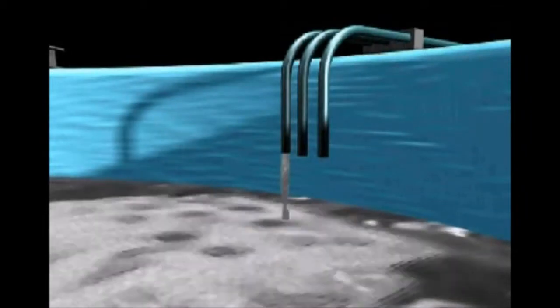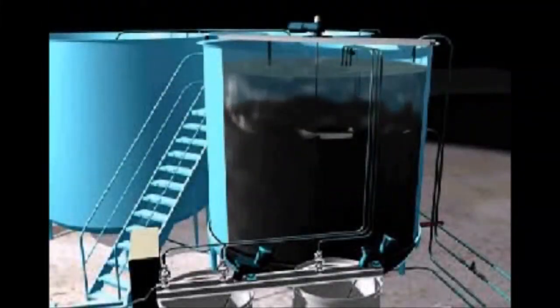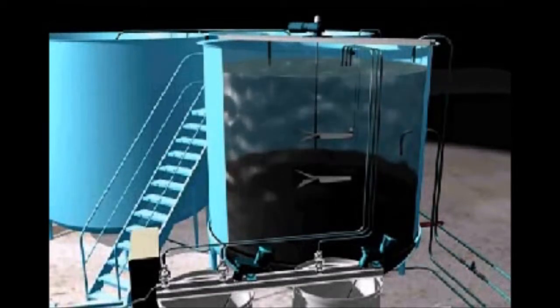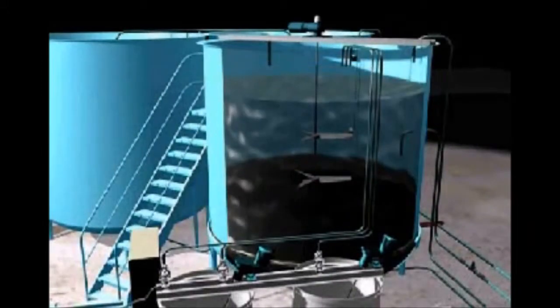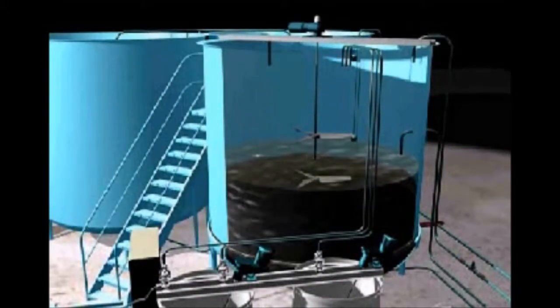The flocculant is then added by volume, after which the mixer turns on for a short time to mix the contents of the tank. The flocculant enlarges the coagulated wastewater for ease of settling and the ability to dewater the sludge in the filter press later. The system then begins the settling phase, where the floc, now called sludge, settles to the bottom of the treatment tank. Once the settling phase is complete, the system transfers the clarified water to the filter press. This stage ends once the water reaches the mid-float level sensor.